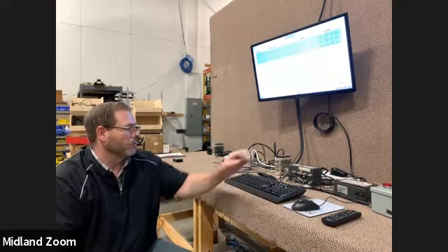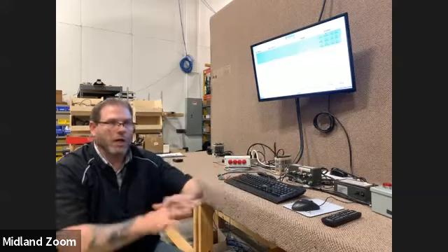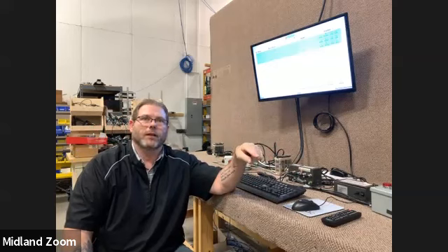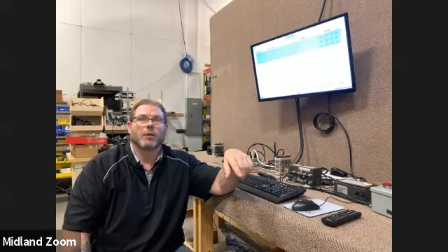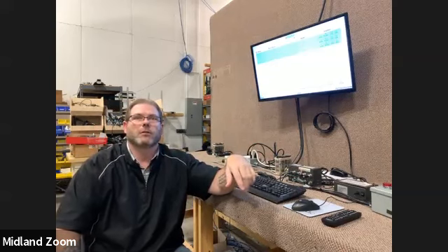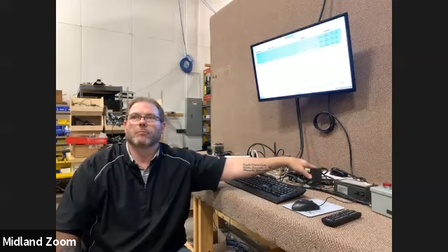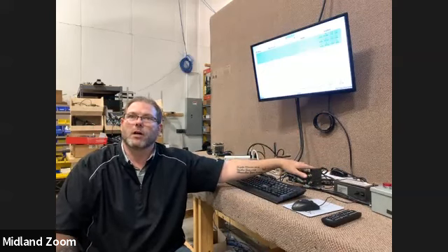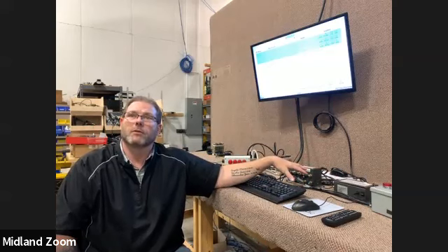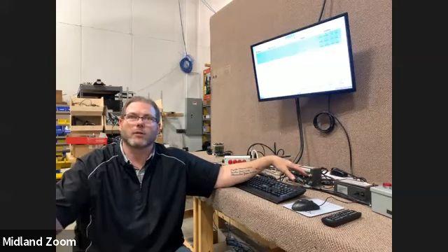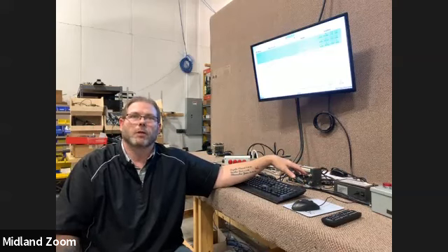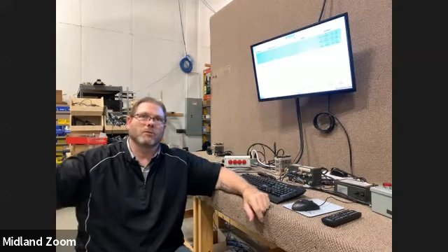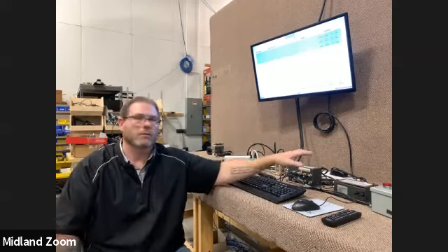Nice. The nice thing about having the 8 inputs and outputs is if your lines are relatively close together, and let's say you want to detect if the conveyor is getting backed up on 8 machines, you can do that with 1 IMAX and 1 reel. So you don't need one for each machine. Right. Because with the 8 inputs and 8 outputs, you can have 8 separate sensors coming into this. If a sensor is blocked for X seconds, it says the line's backed up, and we can pause that machine. Now that one's backed up, we can pause it. We can light lights. So you can do up to 8 different machines.